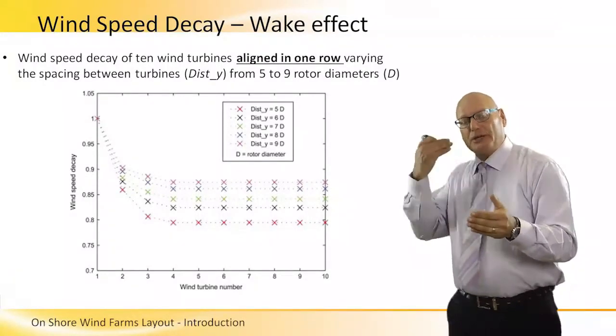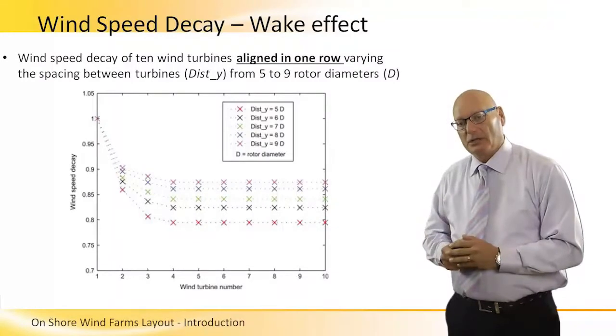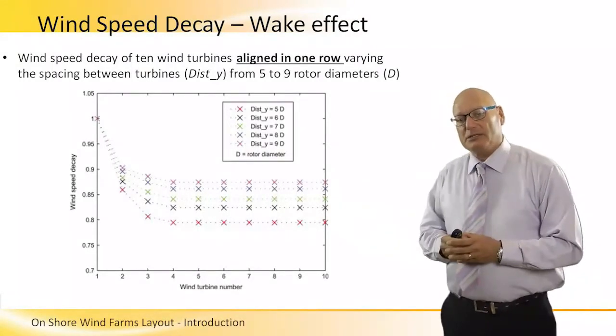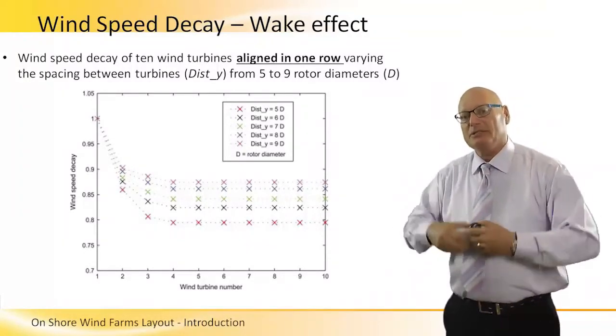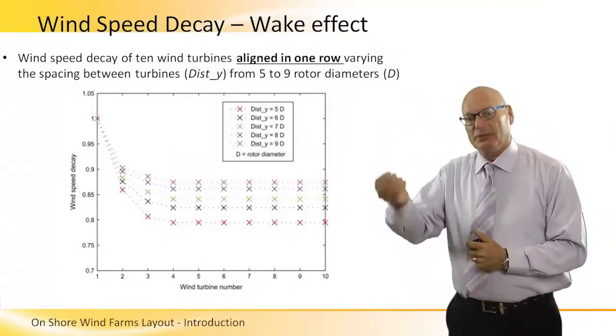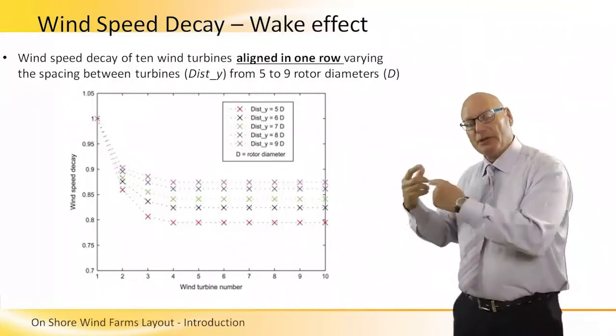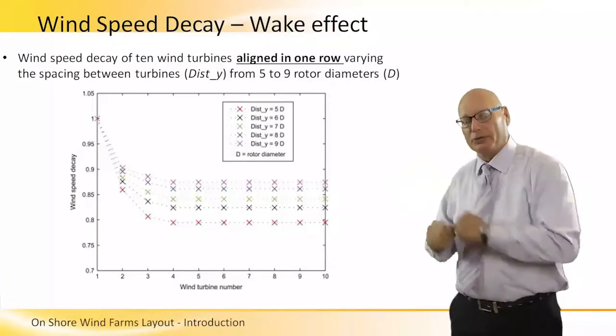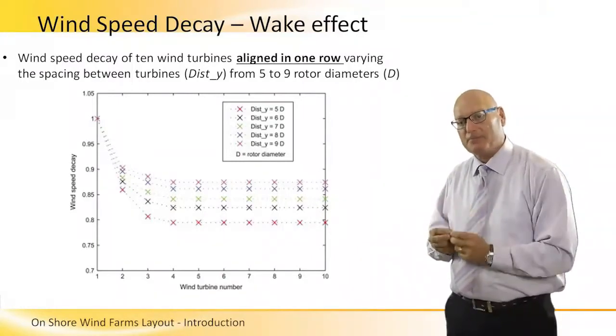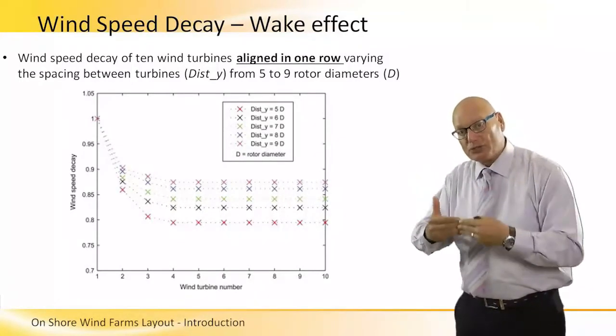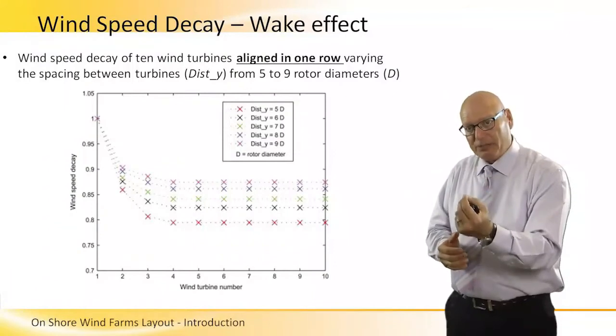As we go further back in the rows, wind speed decreases as we increase the number of turbines. Increasing turbine count means we shorten the distance between them in a given area, which means wake effect is increased, wind speed is decayed in the back rows, efficiency goes down, and output power goes down. This reveals a very interesting relationship between the number of turbines, the number of rows in the array matrix, and the wind speed decay effect.